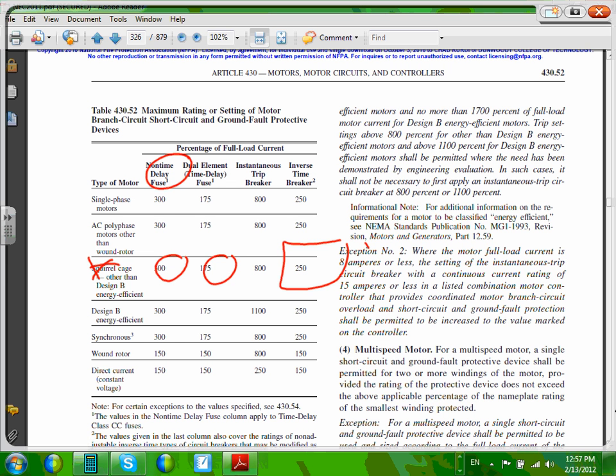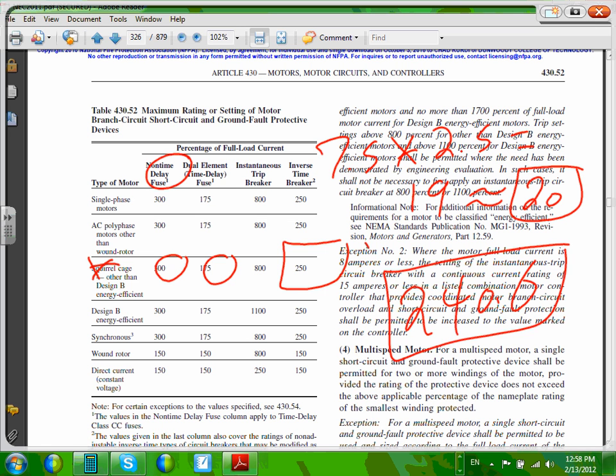Where did you get the table based on number 20? Where did I get what? The number 20 for the inverse breaker? Oh, for the breaker. For the breaker, it was 7.5. 7.5 times 2.5 equals 19 something. Then you go to the next standard, which is 20. Where's that table? Which table? You're going to go to table 240.6 to find which standard.